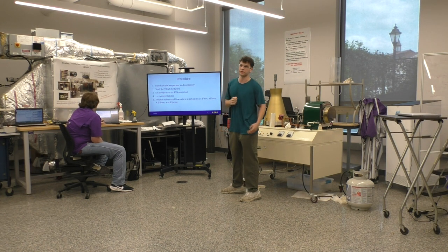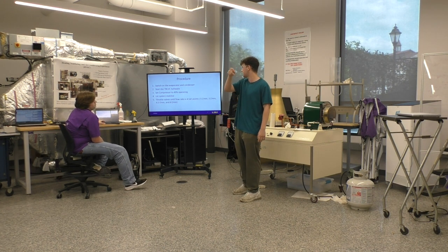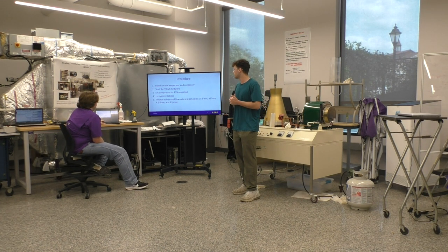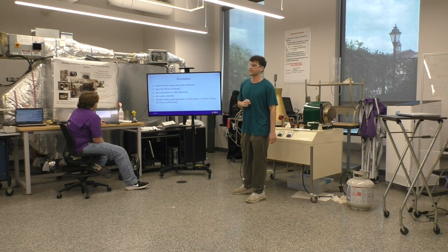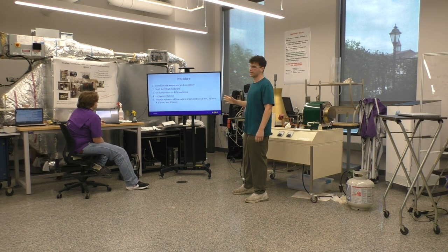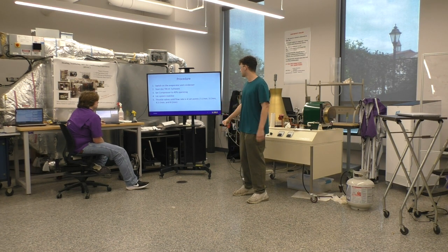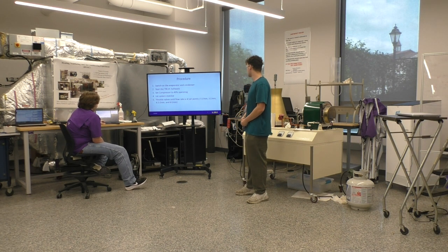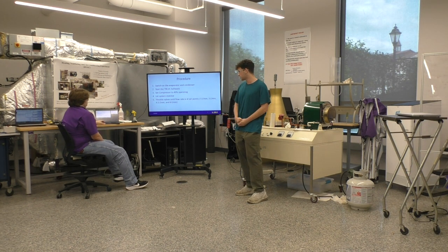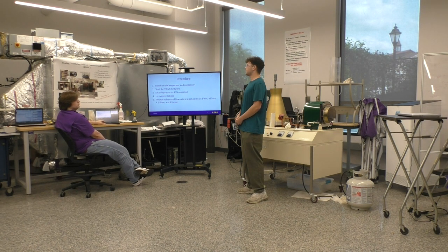So what is the procedure? First step is to turn on the TRCVC and to start the software. Once we have that, we want to set the compressor to 40% to make sure that we are not operating or damaging any of the components. We're going to let that system stabilize, and using the valves at the bottom pumps, we will be throttling the flow rate to set at 5 liters per minute, 3 liters per minute, 4.5 liters per minute, and 6 liters per minute to get different data points.